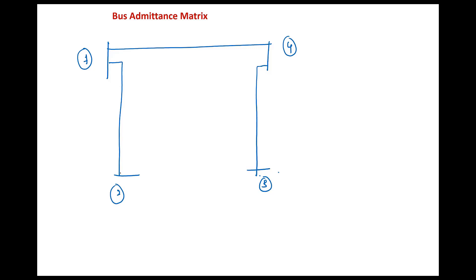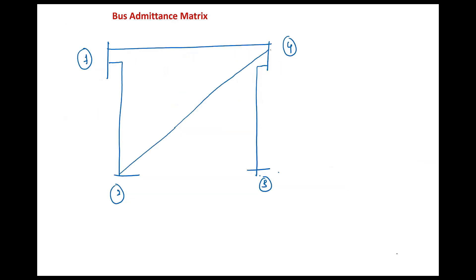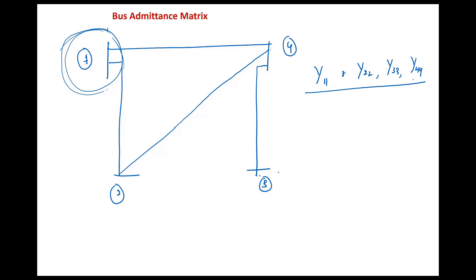Since two lines are missing, four elements in the Y-bus matrix are zero. Properties of the Y-bus matrix: (1) Size is n×n for an n-bus system. (2) It is a symmetrical matrix because the power system network is passive. (3) Most elements are zero, making it a sparse matrix, since it is not possible to connect every bus with every other bus.